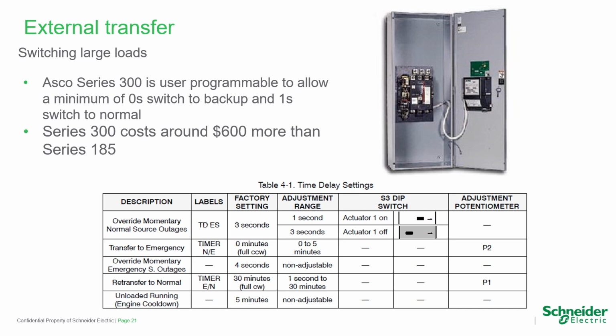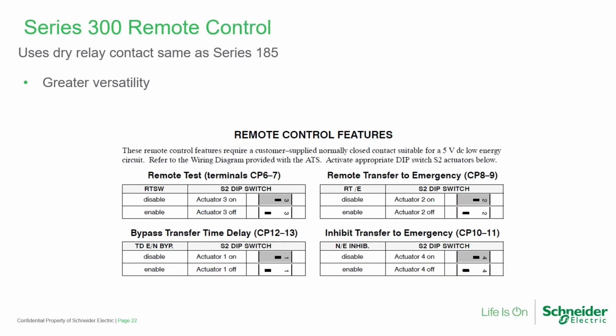Now, the Series 300 ASCO transfer switch offers greater flexibility when specific delays are required, such as longer generator warm-up times for colder environments. It is a bit more expensive. As far as the adjustability, transferring to emergency can be set to 0. Retransferring to the normal position can be set as low as 1 second. So you have a complete range of programmability with the Series 300 transfer switch, and it does cost about $600 more than the Series 185. The ASCO Series 300 has the same external control functions as the Series 185, but adds one more called the inhibit transfer to emergency function.